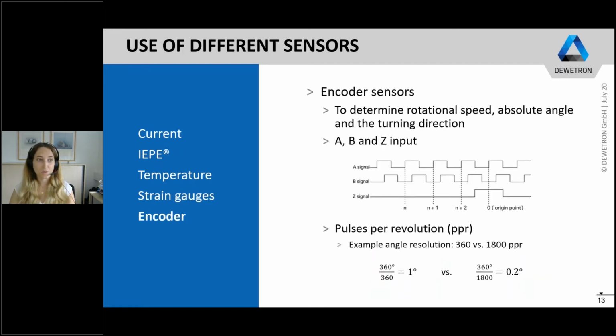The last sensor I would like to talk about are the encoder sensors. These are used to determine rotational speed, absolute angle, and the turning direction. Therefore, they usually have three inputs, A, B, and Z, whereas the A and B inputs have a 90-degree phase shift in order to determine the turning direction, and the Z signal outputs an impulse per revolution to have the absolute angle precision for each revolution.